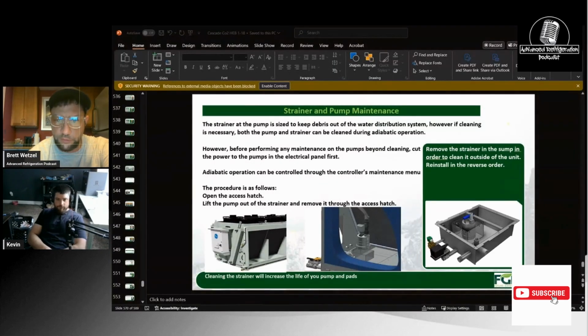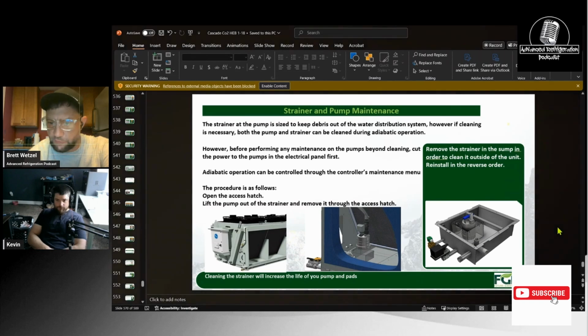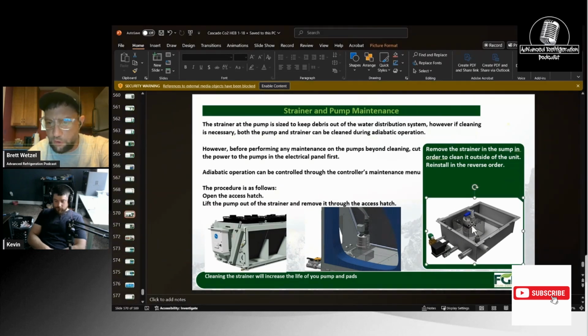Yeah. So right over here, this is essentially what the basin looks like. You have your pump in here. Be mindful, there are holes all along the outside of the pump, but underneath, there's going to be a certain number of holes. That number of holes tells you how many fans it belongs with. If it has 3 fans, then it's a singular pump, and it's going to have 3 holes right in the middle of the pump. If it is a 6 fan, you'll have 3 fans over here, 3 fans over here. You'll essentially have three holes on there, but you'll have 2 different pumps.